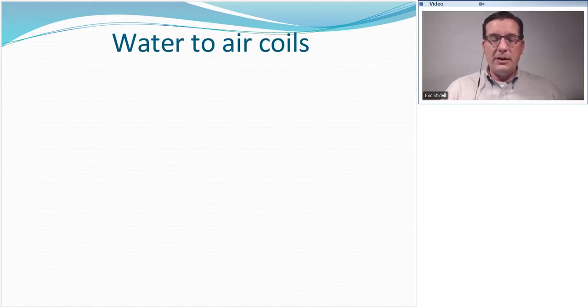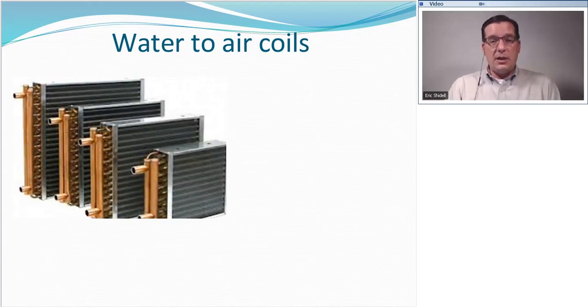Some other types of heat emitters we're going to talk about are water-to-air coils. These are just like the radiators in your car, or very similar to the evaporator or condensing coil in an air conditioning or refrigeration system. Essentially, we've got a series of copper tubes running back and forth with aluminum fins in between to expand the surface area and allow us to transfer that heat from the water through the copper into the air.